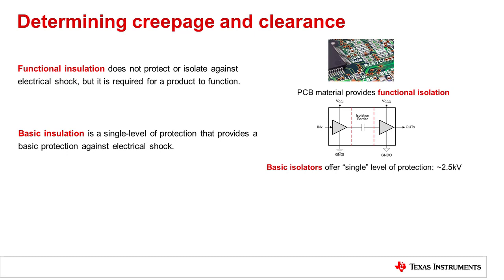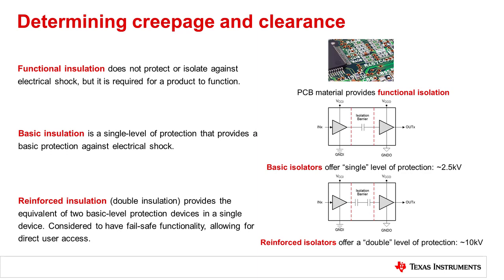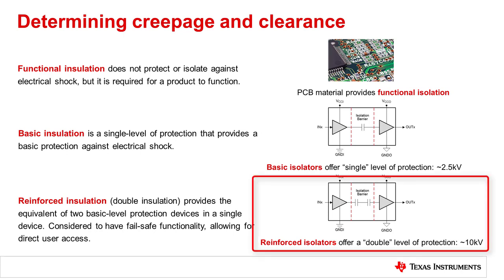If the basic insulation fails, there is exposure to hazardous voltage. For integrated circuit isolators, the term basic isolator describes isolation that acts as a single level of protection for voltages typically between 2.5 to 3 kV and occasionally as high as 5 kV. Reinforced insulation, or double insulation, provides the equivalent of two basic level protection devices in a single device and is also considered to have fail-safe functionality, allowing for direct user access. This does not mean there are two devices in a single package, but that the tested insulation of a reinforced isolator performs at twice the level of a basic isolator.